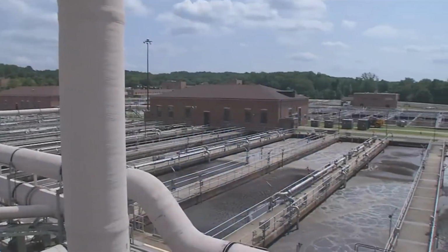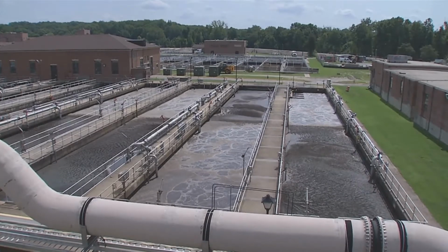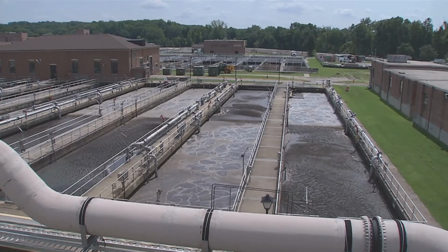For this lab, we're going to focus on the importance of removing ammonia and other nitrogen compounds from our wastewater. At Nome & Cole, secondary treatment consists of two processes, our ASTs, or activated sludge tanks, and secondary sedimentation. The ASTs are where we add these microorganisms, and the wastewater travels between two zones, those that we add oxygen to and those that we don't.